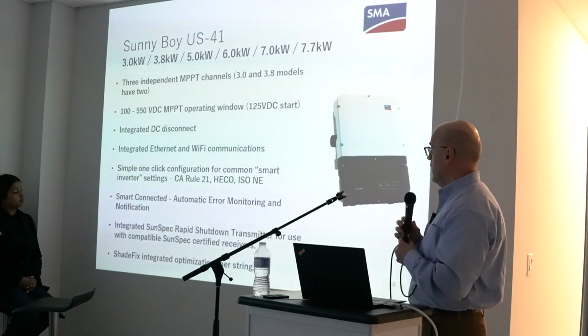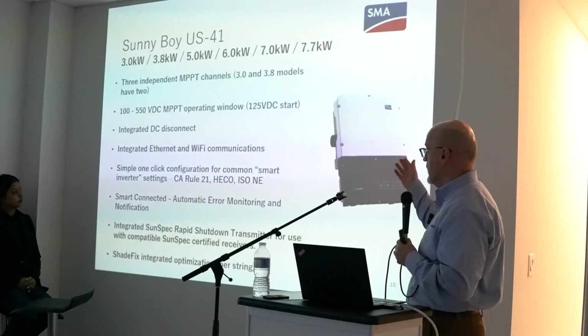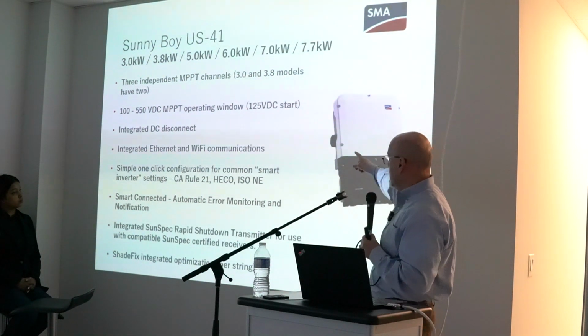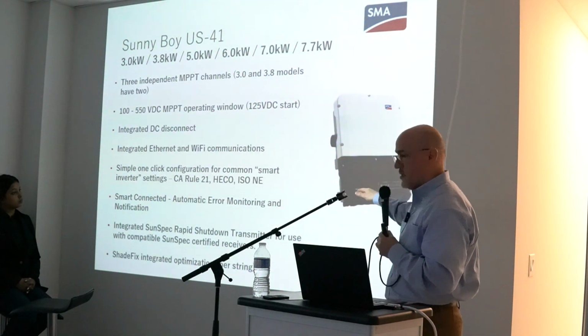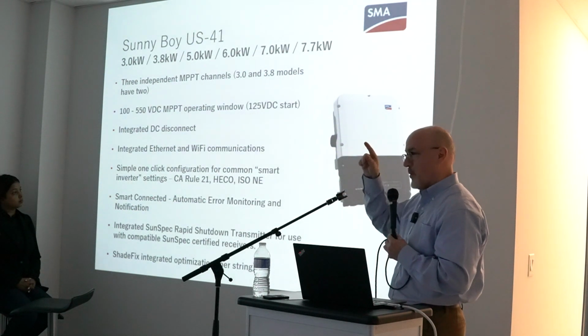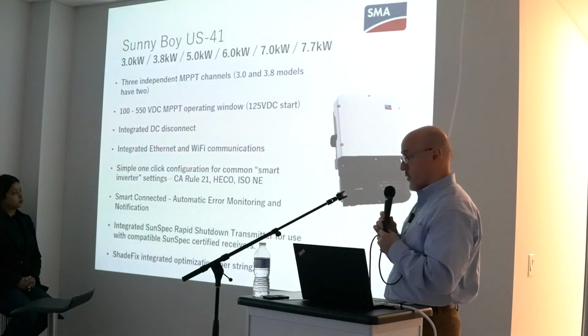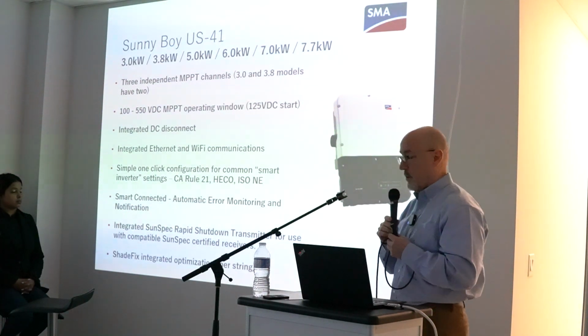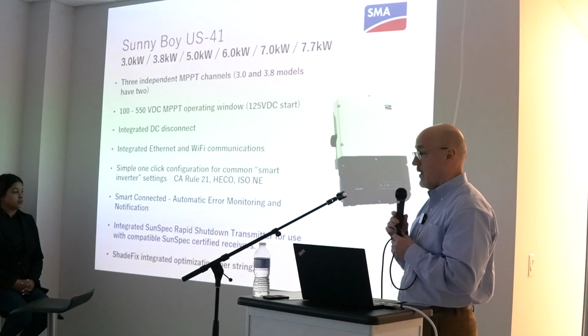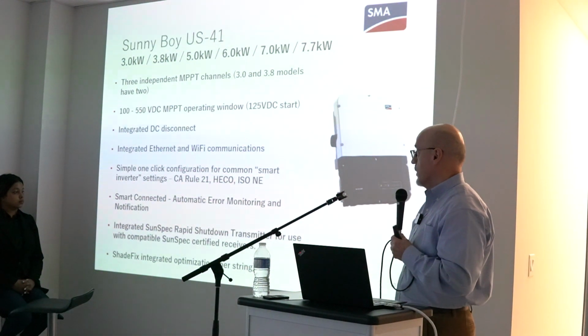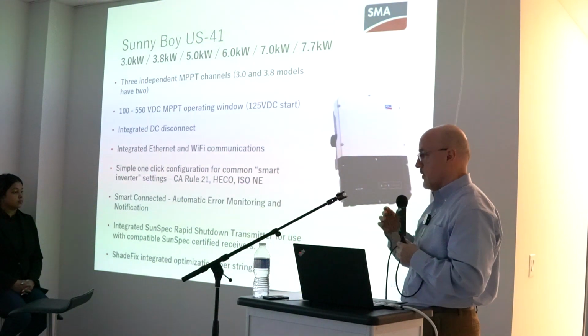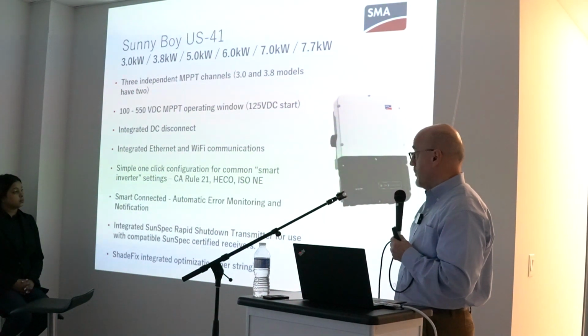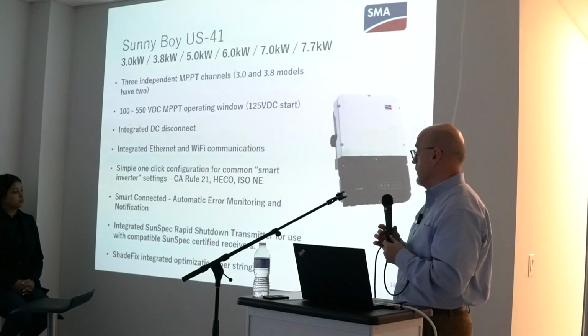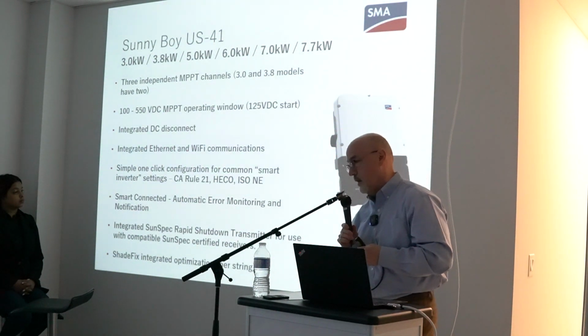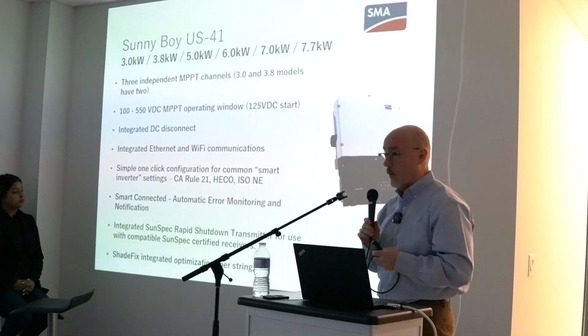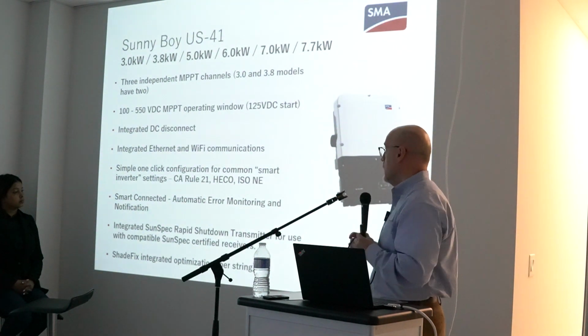Some of the functionality in this product, as noted here, includes a DC disconnect. From a communication standpoint - and I'll put an asterisk on this - we have Ethernet communications, 2 hardwired Ethernet ports, and Wi-Fi communications for commissioning the inverter, if you want to commission it from a laptop or something like that, right from Wi-Fi. Likewise, you can communicate via a Wi-Fi router back to our monitoring portal.